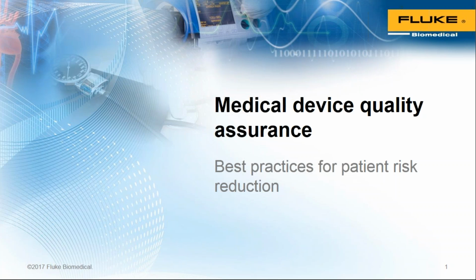So typically we look at it this way. If we look at the international standards, the IEC 60601-1 is the standard that the manufacturer is required to meet in the process of proving that their medical device is safe and effective for clinical use. That earth bond test, the protective earth resistance, requires a 25 amp current flow in order to make the resistance measurement. And I go into much more detail about that in the electrical safety course that is in the Advantage Training Center. So I ask you to please go look at that and work through that course.